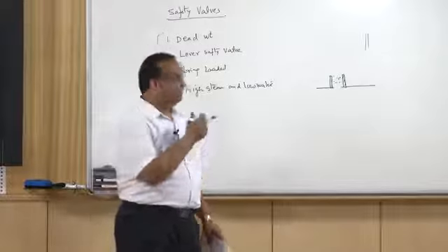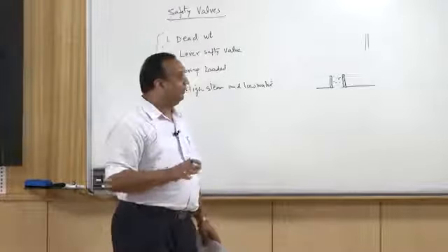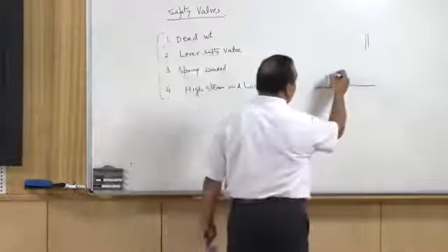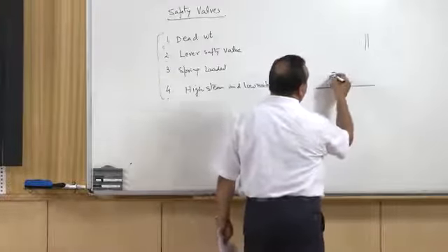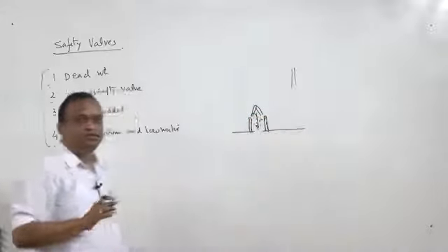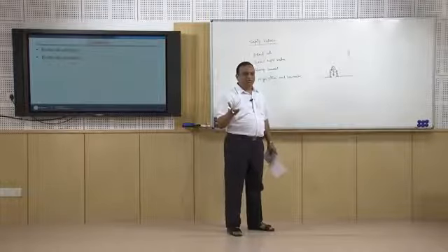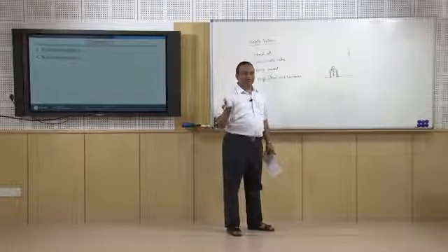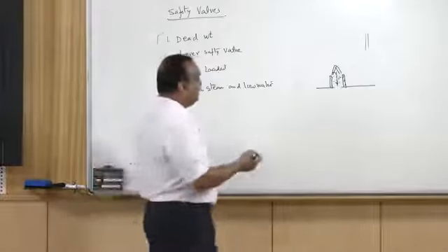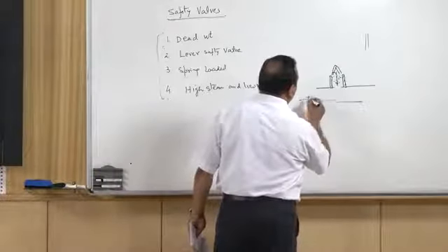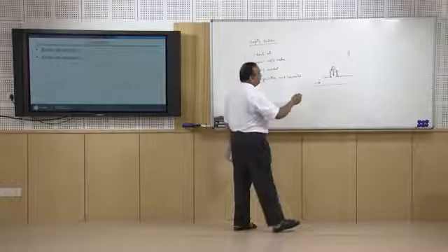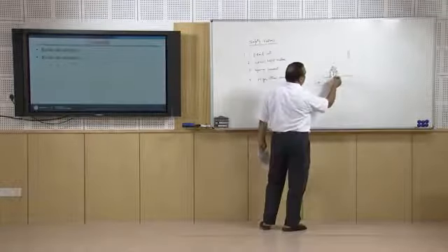But in this case the boiler will shut down. I mean, it cannot operate in a running boiler. Once this fusible plug is operated, the fusible material, it has a copper cap also, right. So when the material is melted, the water will enter the fire tube, it will go to the grate, or it will take away heat from the fire tube, or the flue gases flowing in the fire tube, and ultimately the heating in the boiler will slow down, or it will be reduced, right, and in that case the accident can be prevented.